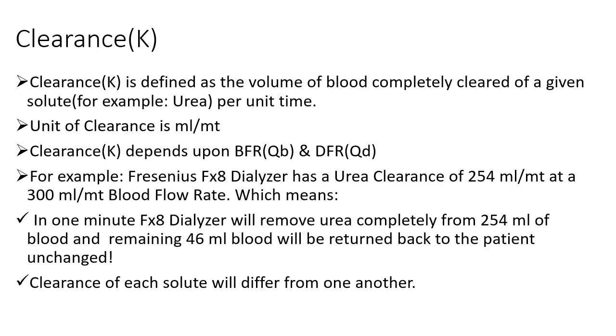Let's discuss clearance first. Clearance, or K, of a dialyzer is defined as how completely a dialyzer can remove a particular solute — for example, urea. The solute can vary; it may be creatinine, inulin, or beta-2 microglobulin.